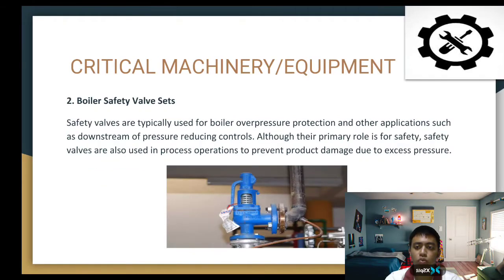The number 2 critical equipment is the boiler safety valve sets. Safety valves are typically used for boiler overpressure protection and other applications such as downstream pressure reducing controls. Although their primary role is safety, safety valves are also used in process operations to prevent product damage due to excess pressure. So the safety valve is a helpful device to prevent excessive pressure, such as air, that can also cause a fire, because it is an element of a fire triangle.